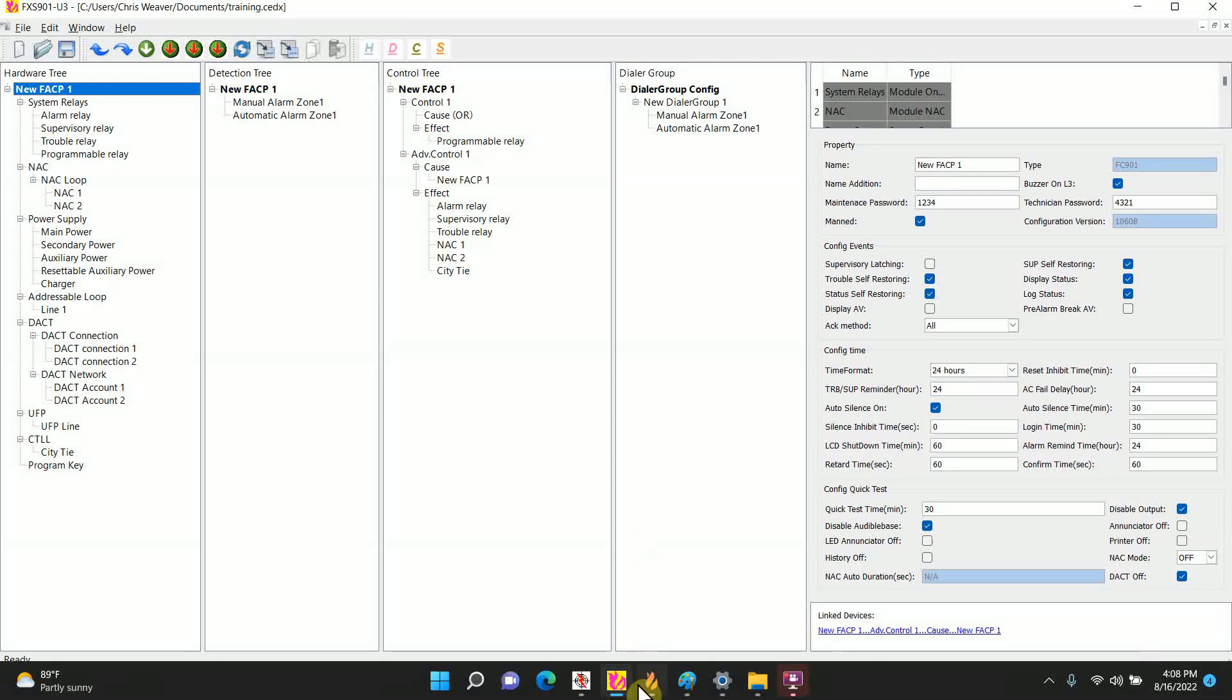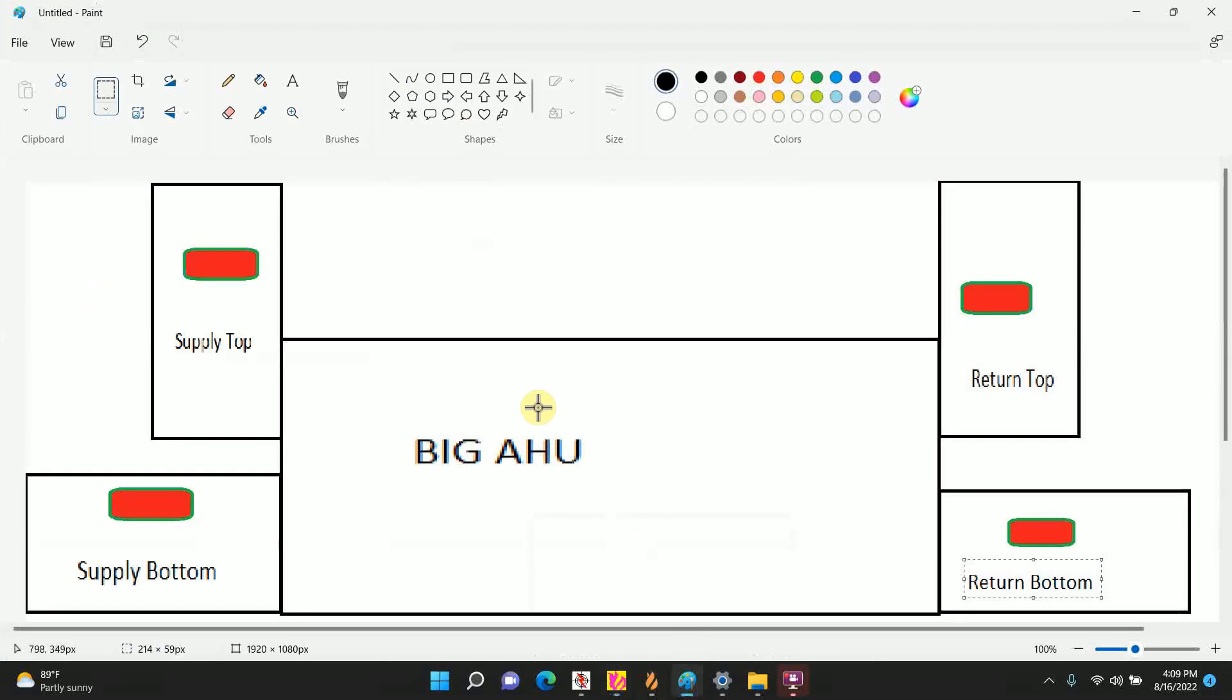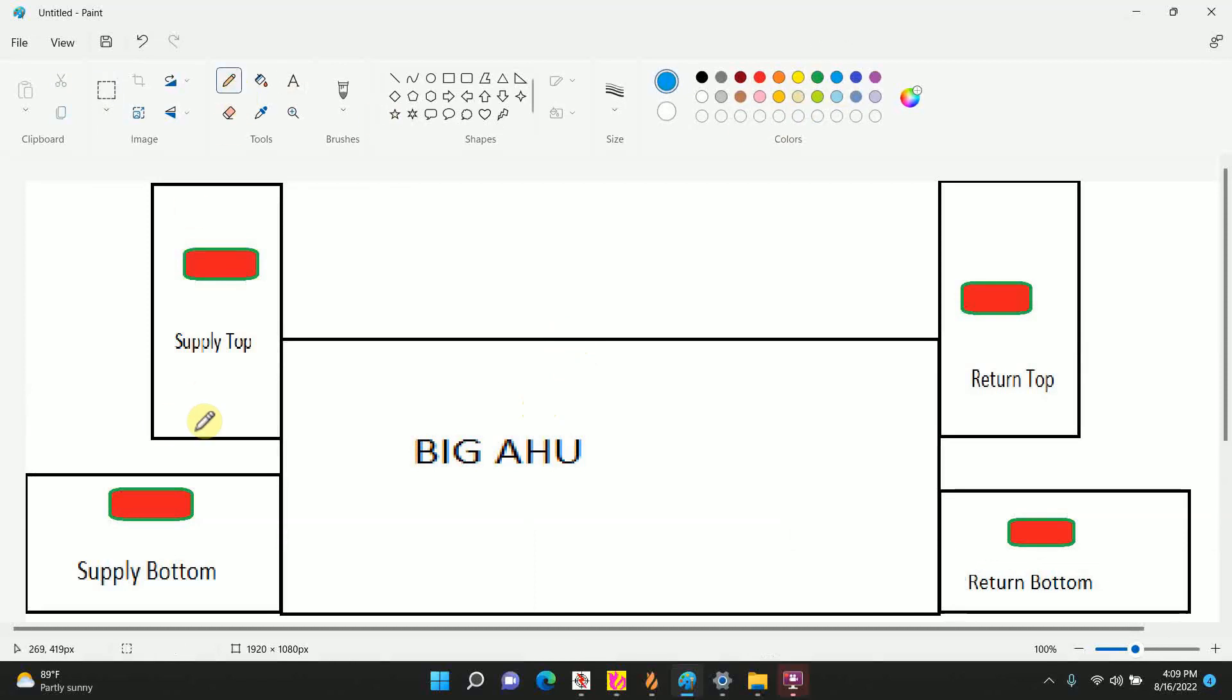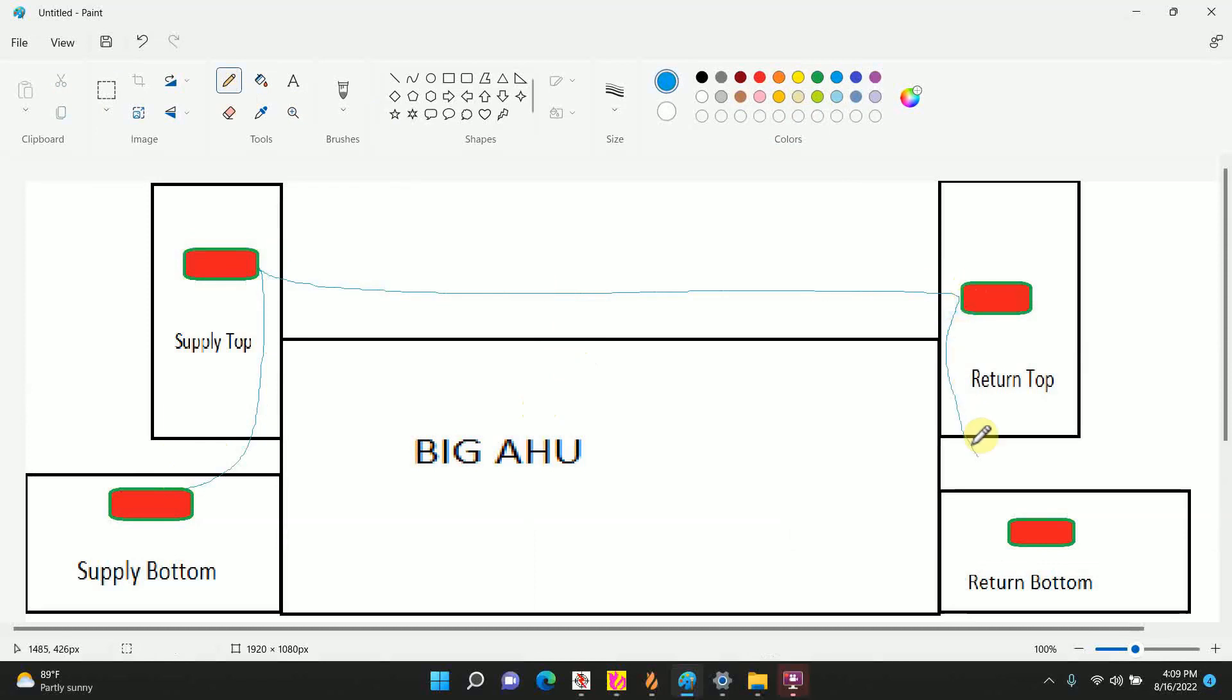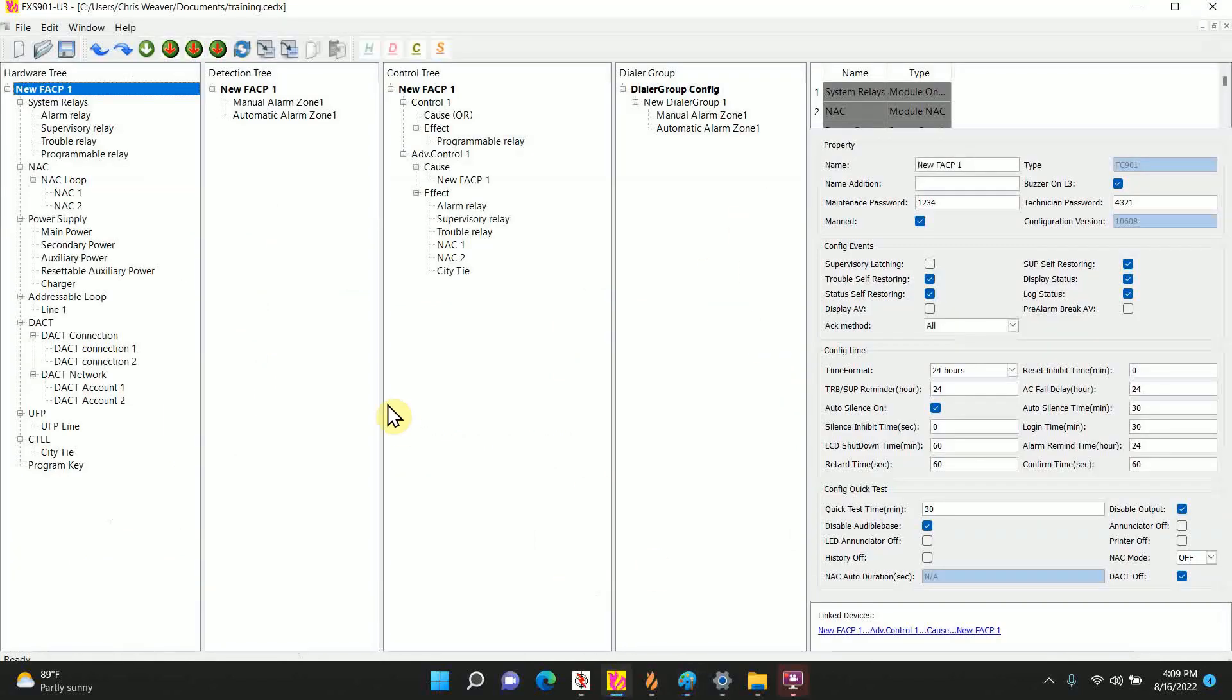And a scenario where in this picture here we're going to have a big air handler unit and it actually has four duct detectors hooked up to it. I've had previous people and they would do something similar to this, knowing that there's one shutdown where I'd run one wire to each and every duct detector, do all the relays to finally get to the shutdown. I'll show you how to eliminate that and run it to the nearest duct detector for ease of wiring, ease of relay logic. Let's go ahead and start with the 901 programming.